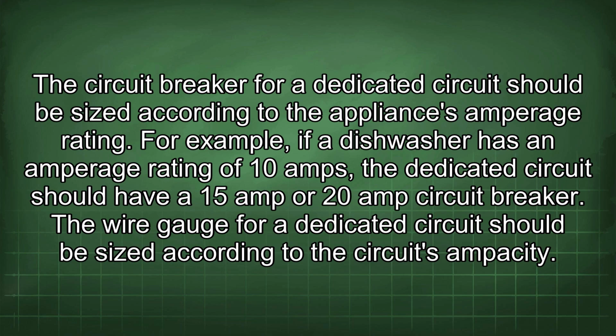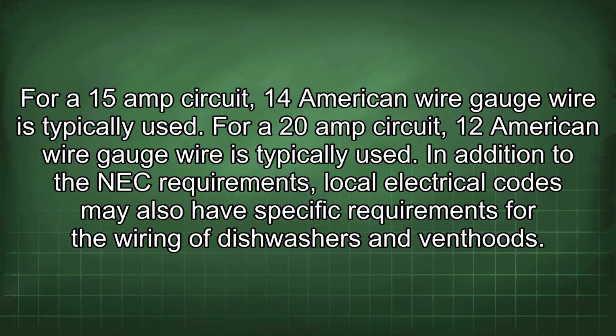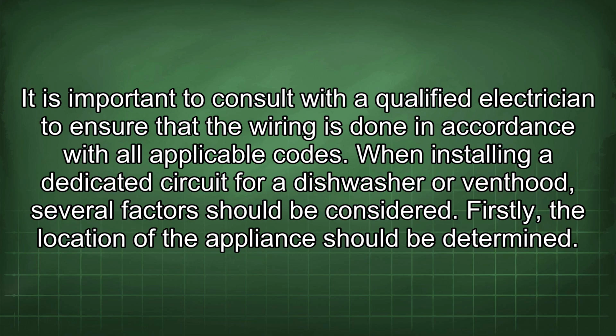The wire gauge for a dedicated circuit should be sized according to the circuit's ampacity. For a 15 amp circuit, 14 American wire gauge wire is typically used. For a 20 amp circuit, 12 American wire gauge wire is typically used. In addition to the NEC requirements, local electrical codes may also have specific requirements for the wiring of dishwashers and venthood. It is important to consult with a qualified electrician to ensure that the wiring is done in accordance with all applicable codes.